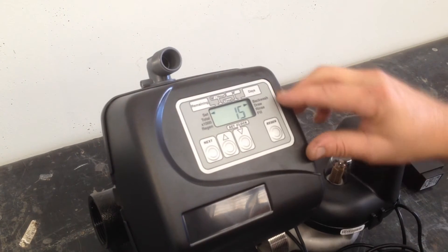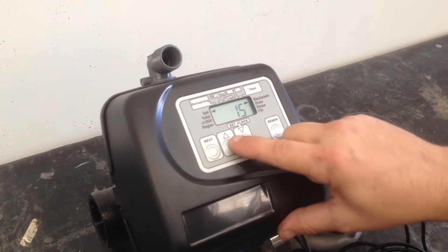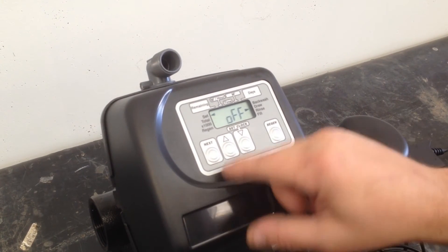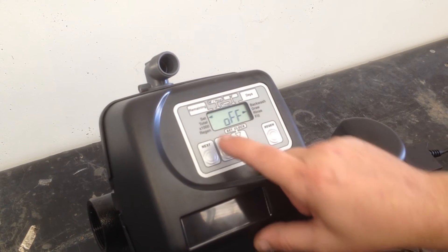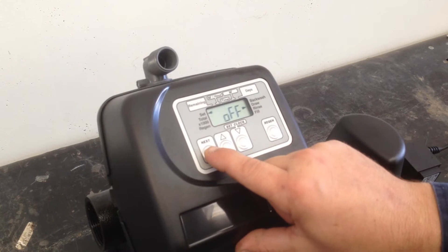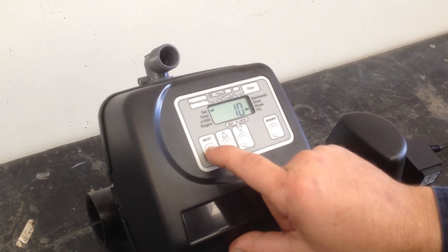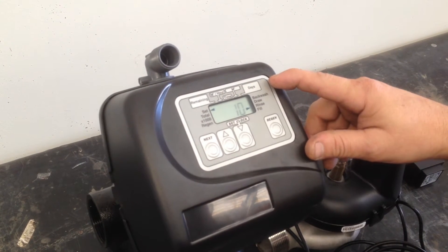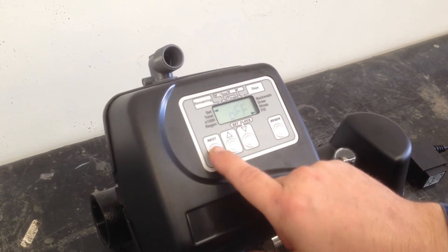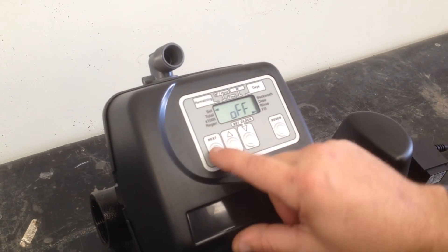Now we're looking at our backwash lengths — how long it's going to backwash for. To change that, use up or down, then next. Brine draw: we do not have a brine draw in a filter, so that's off — go next. Our second backwash is off, go next. Our fast rinse, which is where we're dumping water down through the bed, is 10 minutes. Next. Fill — this is where we'd put water back to the brine tank if it was a water softener; it's not, so it's off.